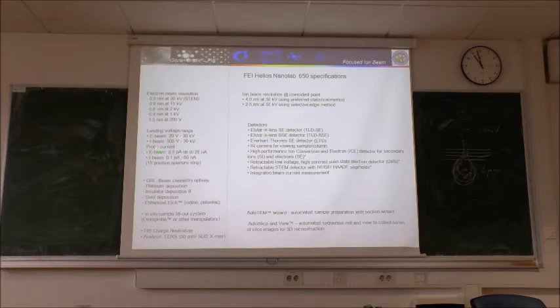Probe current, you see, is from 0.8 picoamperes to 26 nanoamperes. It's a really huge range, also for the ion beam. So in that case you are really polishing and using a very, very artistic approach, and in that case you are using dynamite, or these big cranes. We have 4 different gas injection systems. We can deposit platinum, an insulator which is based on silica, silicon oxide, gold, and we also have enhanced etching using iodine, so that we can improve etching by a factor of 10 or 20, just due to the chemical reaction of the surface atoms with iodine.